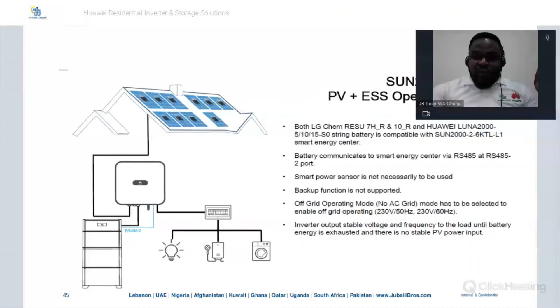My last but one application here, as I mentioned, you can mix and match. There's the synchronization. This is a 3 kilowatt inverter mixing with a 2 to 6 kilowatt inverter with batteries in the same system, connecting to a three-phase grid, and you don't have a problem. So that's a three-phase inverter, that's a single-phase inverter, that's a single-phase inverter, all synchronized, each one has a backup box and all sent to the grid.